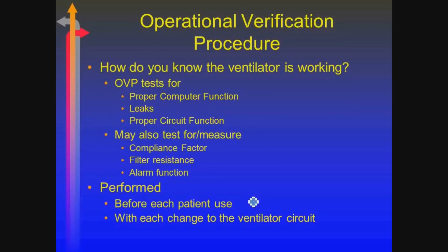It'll tell you if your circuit's functioning, especially if you have an external valve. It also will then go ahead and measure, on some of them at least, what that circuit factor is, the compliance, the compressible volume factor, what the resistance of the filters are, and will verify that all the alarms are working. And that should be done before each patient use.